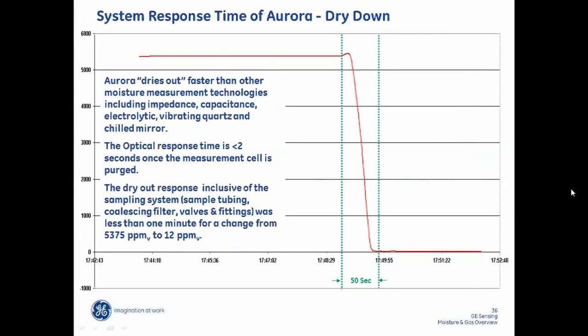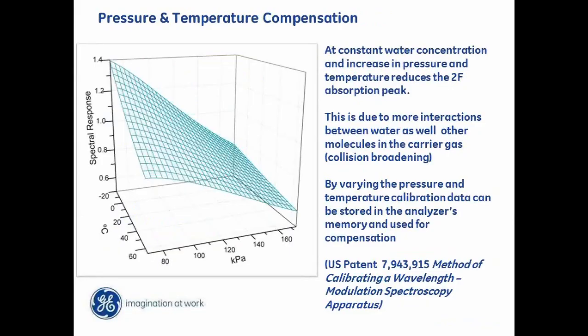Now, the Aurora system is patented in the sense of our pressure and temperature compensation. So in order to give greater precision, we vary the temperature and pressure and record that data into a matrix as well. Absorption, as you increase the pressure, you get this phenomenon called pressure broadening. And that's because you have more interactions between water itself, between water molecules, as well as the other molecules. So you don't get the predicted absorption that you normally would because of this collision broadening. And temperature has a very similar effect. So we're able to compensate for that or adjust for that by ramping the system through pressure and temperature and then storing that data into the unit's memory as a lookup table. And it works very effectively to give us very good precision.